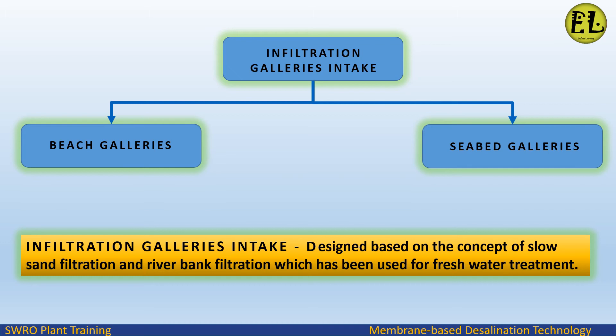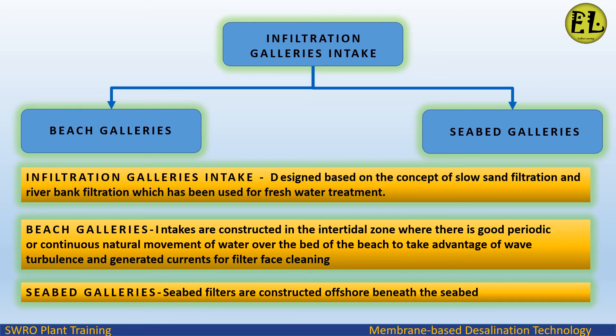Infiltration gallery intakes are designed based on the concept of slow sand filtration and river bank filtration, which has been used for freshwater treatment. Beach gallery intakes are constructed in the intertidal zone where there is good periodic or continuous natural movement of water over the beach bed, taking advantage of wave turbulence and generated currents for filter face cleaning. Seabed gallery filters are constructed offshore beneath the seabed.